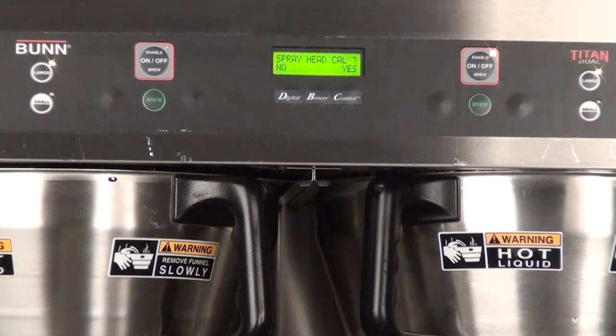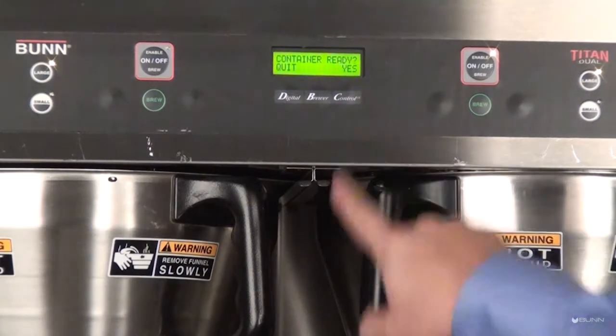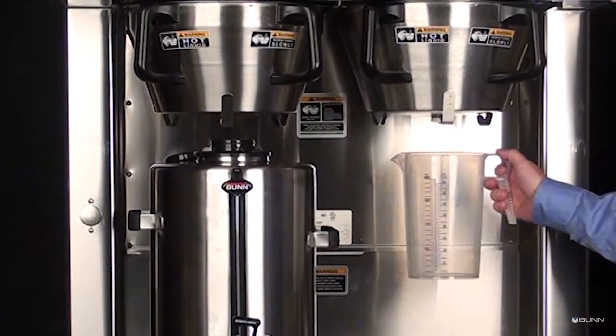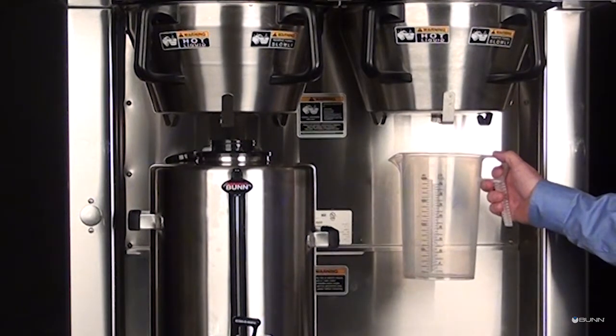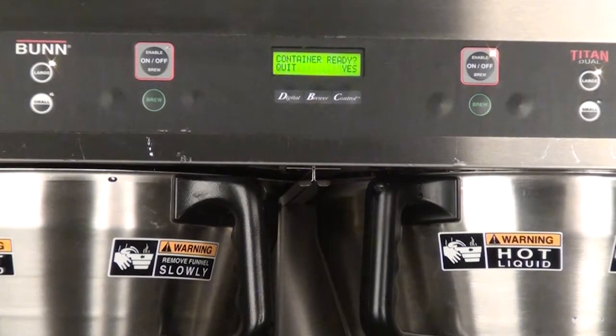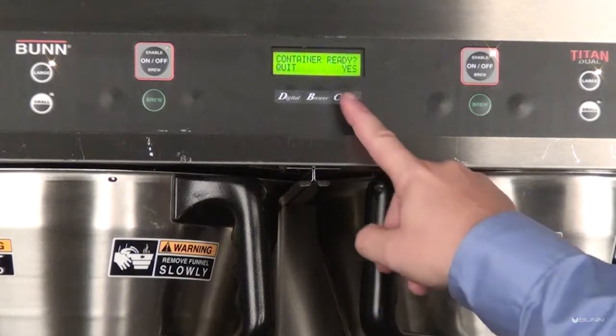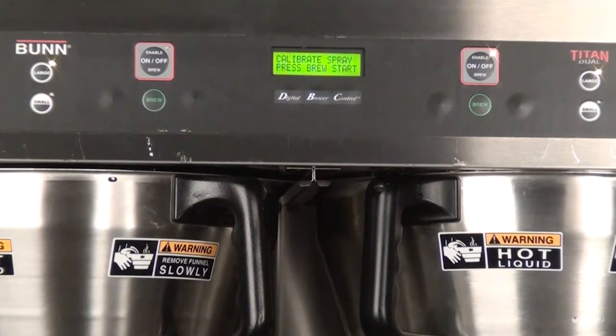The display screen will now read Spray Head Cal. Select Yes to accept the spray head calibration option. Place a container, accurately graduated and with a minimum capacity of 60 ounces, beneath the funnel. The display screen will now read Container Ready. Select Yes with the control switch after confirming that the container is ready.